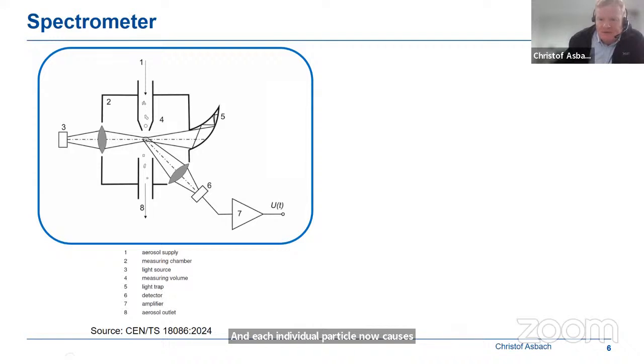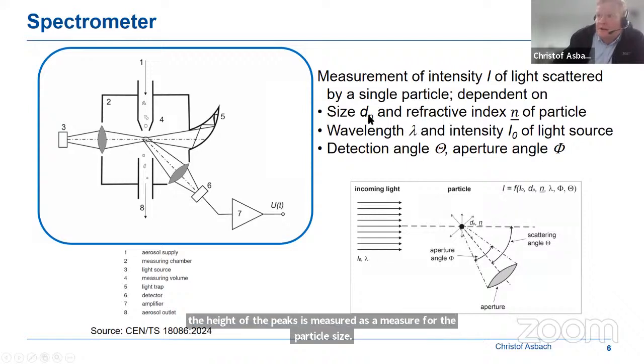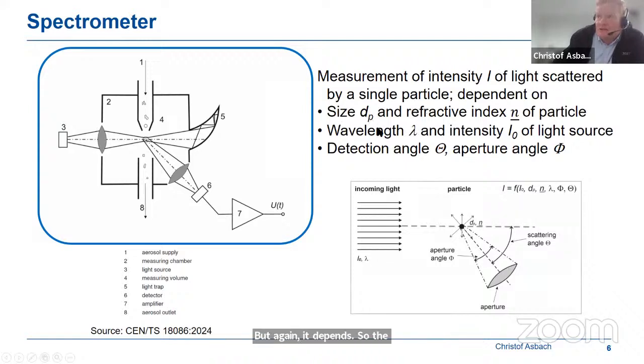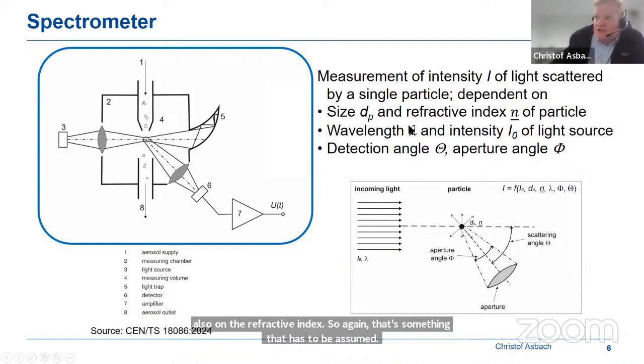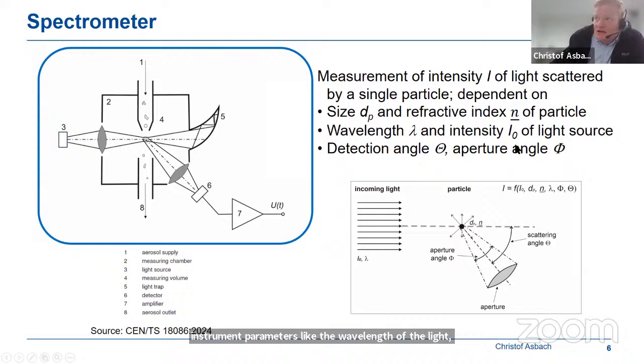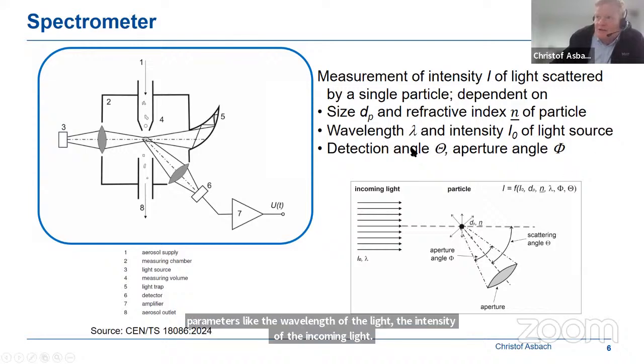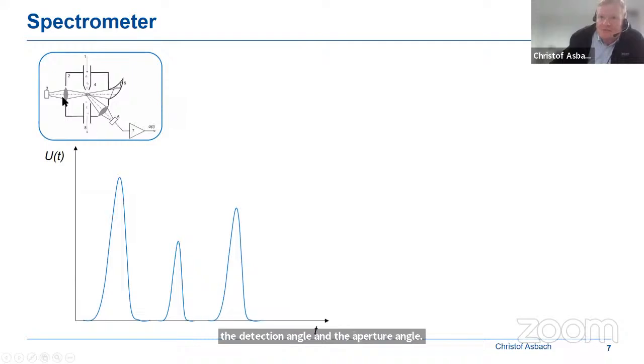peak. And these peaks are counted as a measure for the particle number, and the height of the peaks is measured as a measure for the particle size. But again, it depends. The intensity of the light scattered depends on the one hand on the size. This is what we want because we may get the size information, but also on the refractive index. So again, that's something that has to be assumed. And then some instrument parameters like the wavelength of the light, the intensity of the incoming light, the detection angle, and the aperture angle. Now, as a result, the measurement result here, the voltage as a function of time, looks like we can see here.